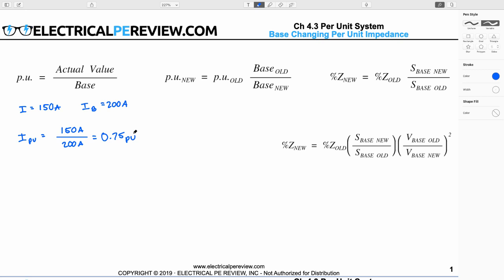Now, what happens when I want to do a base change? This formula over here — I can multiply the old per unit value by my old base, and when I do this, I get back to the actual value. Then I just divide it by the new base to go back into the per unit system, except this time expressed in a new base.